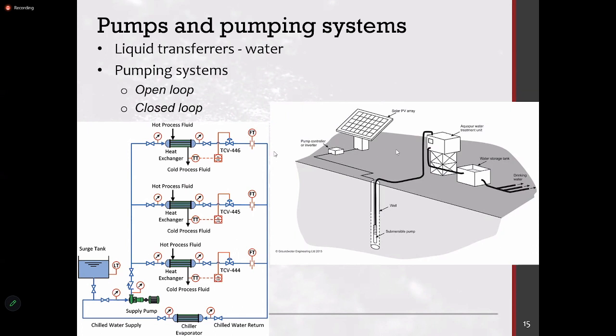So the difference is, in a circulating system, whatever the height you reach, since it's a closed loop, you get a back pressure head. Even at the inlet, you get a head. So the pump should actually supply only the head loss. So you are not supplying the height difference.